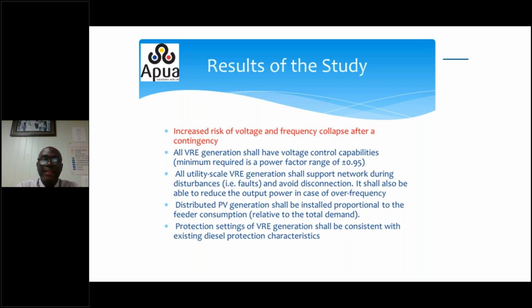They also recommended that all utility scale VRE generation shall support the network during disturbance. Now, this is very crucial because when there's a fault on the grid, you don't want the RE system to be coming off of the grid. You want it to support the fault current, meaning you need a high fault current in order for the protective devices to operate. So if the RE is going to come off of the grid or isolated from the grid, and then the fault current reduces, it means the fault stays on the grid for a longer time. So that recommendation is welcome. Also, distributed PV generation shall be installed proportional to feeder consumption, meaning that on each feeder, you don't want to have excessive RE. So it does affect the stability of that feeder and power quality. And also, they recommended the protection settings of the VRE generation shall be consistent with the existing diesel plants, meaning they must be the same. Next slide, please.